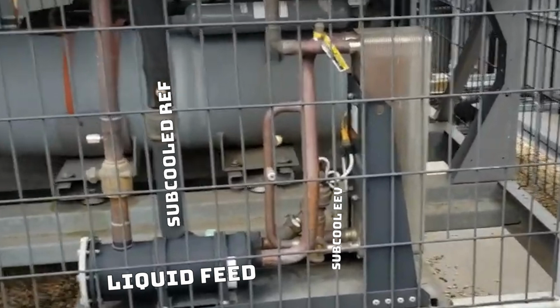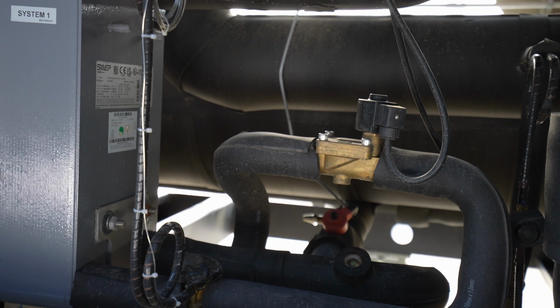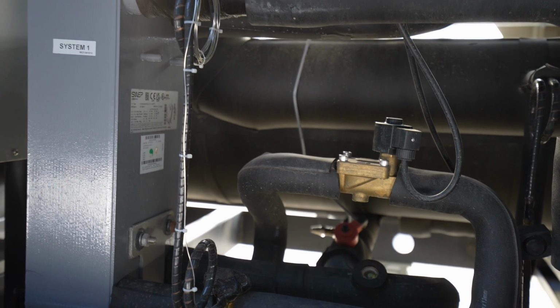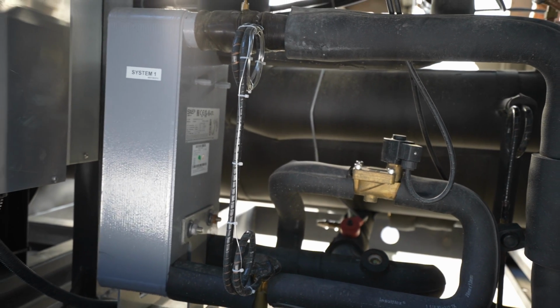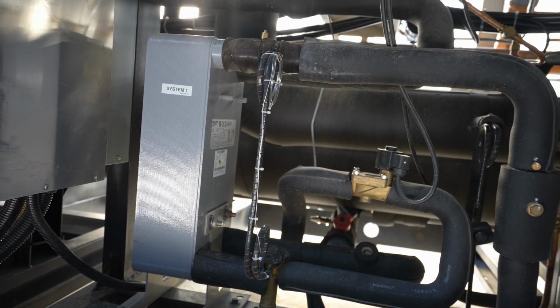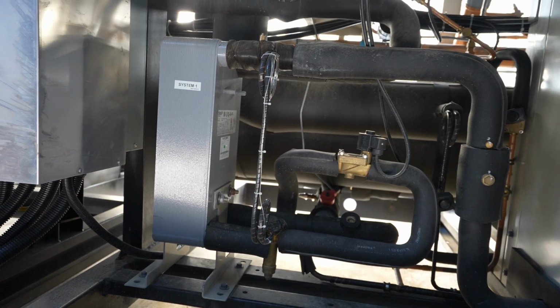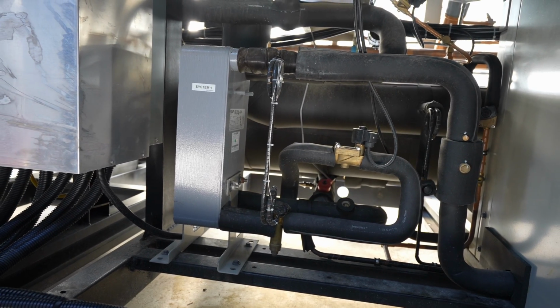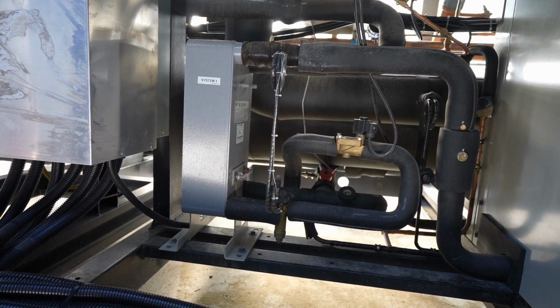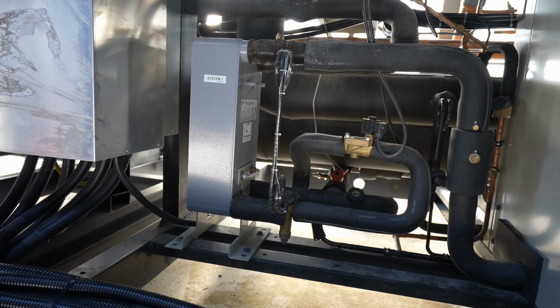This was very commonly done with a brazed plate heat exchanger, and is still a very active practice to this day. Dunham-Bush is an immediate example of they actively use this. So does Carrier with their 30X series. They have brazed plate economizers. Carrier's been doing that for a very long time. So with those systems, we may have 8-10 degrees of subcooling coming out of our condenser coils, entering into the main metering device for the evaporator.